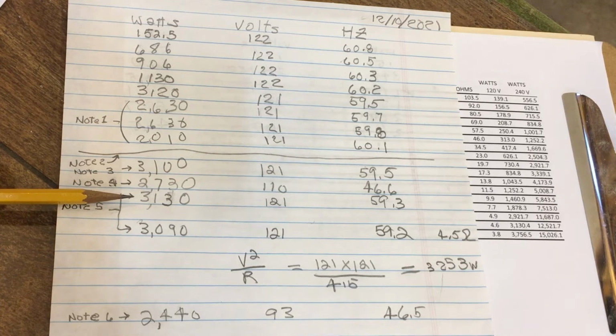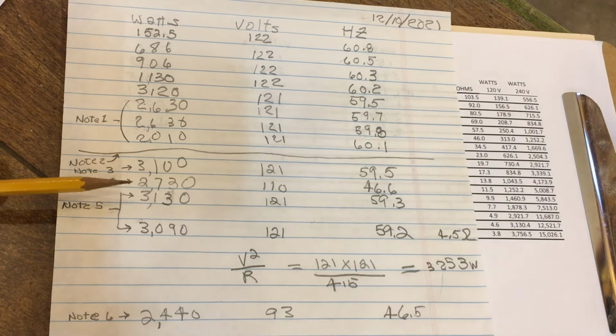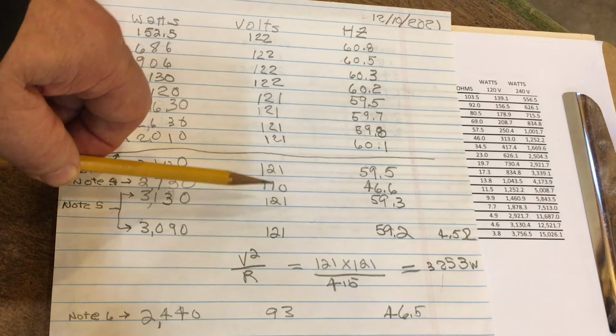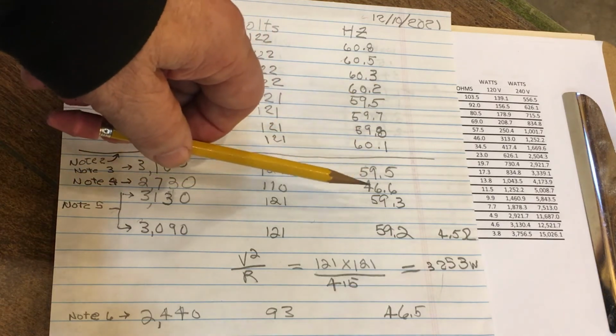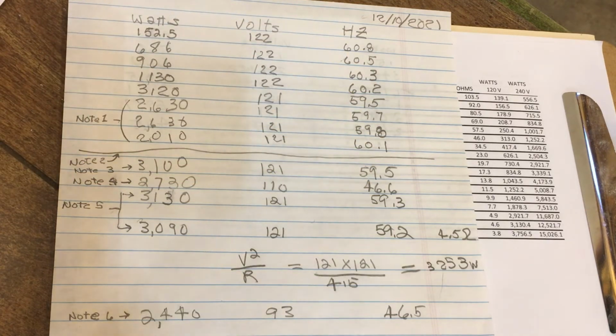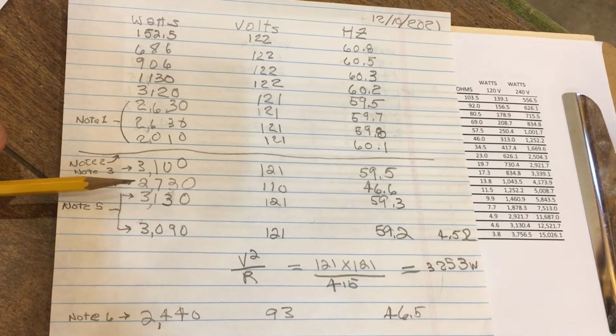I can't explain why the numbers are a little bit different. Could be just the errors in the metering equipment, or maybe the heating elements changed a little bit. Seems like each time you reset to the same position, you don't necessarily get identical numbers again. And again, I had 121 volts, and the frequency was right at 59.3, pretty good.